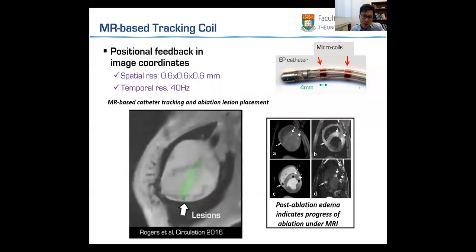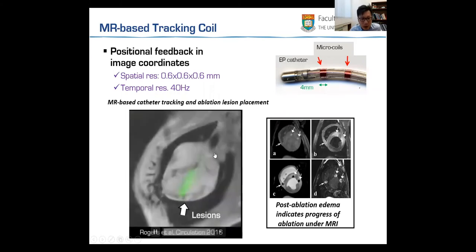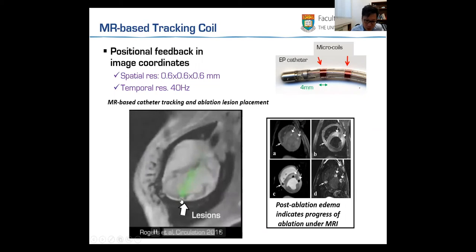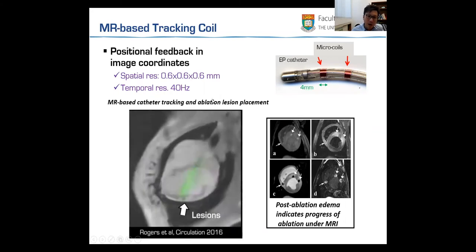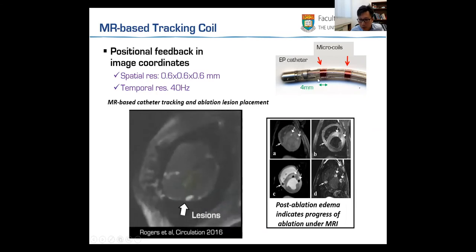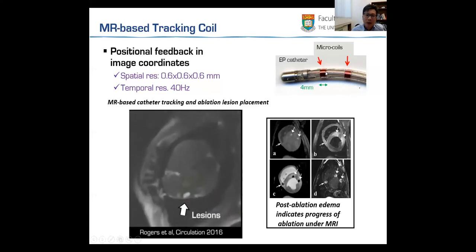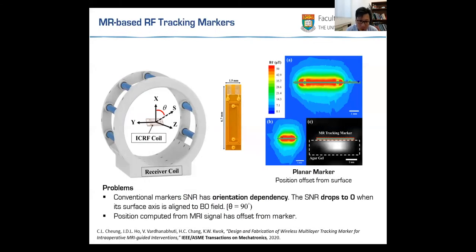Apart from robot actuation, we also have to track the position of the instrument relative to the MRI domain. Here is an example where the green color indicates the catheter tip inside the left atrium, and color changes around the tip indicate lesions being created due to ablations. One key element is the fiducial marker — this is an active one with two solenoid markers connected with four wires to a receiver box, requiring a complicated tune and match process to ensure high SNR signal pickup.